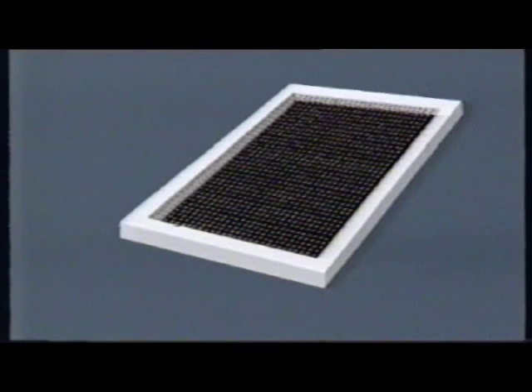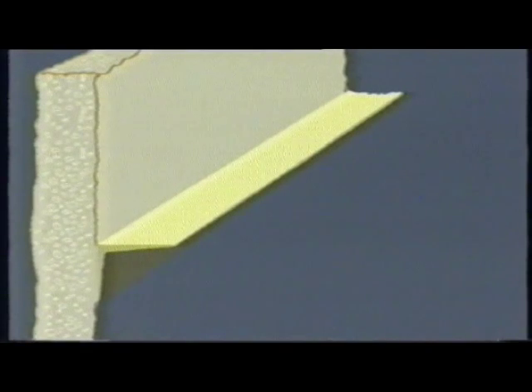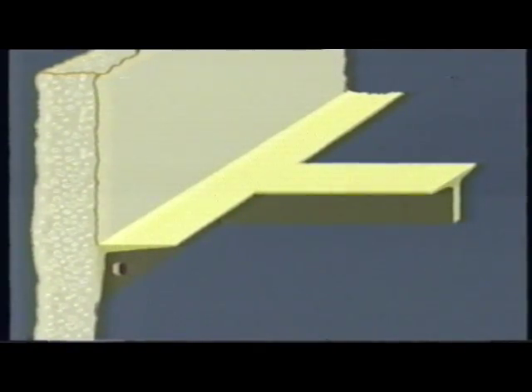The system is constructed using modular panels. Twin polyester filter membranes are mounted around a square box section aluminium alloy framework to form a modular panel. They are then mounted on a rigid GRP angle framework fixed to the tank with T-section cross members at optimum depth to ensure efficient performance. These can be arranged to suit any size of tank.